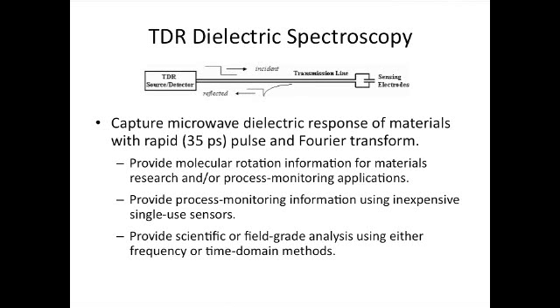Using the TDR approach, we have two different ways of looking at our results. We can either look at it directly as a transient, which is how we capture the data, or we can do a mathematical Fourier transform to get a high-grade scientific permittivity spectrum for laboratory-grade analysis. So we basically have the ability to jazz it up for the laboratory or dumb it down for field use.